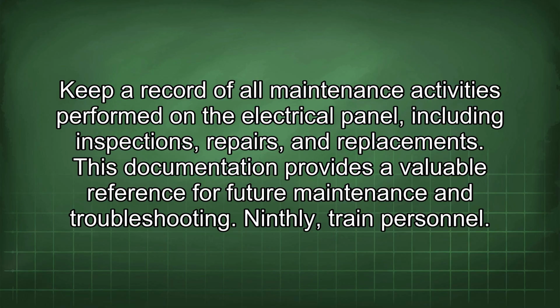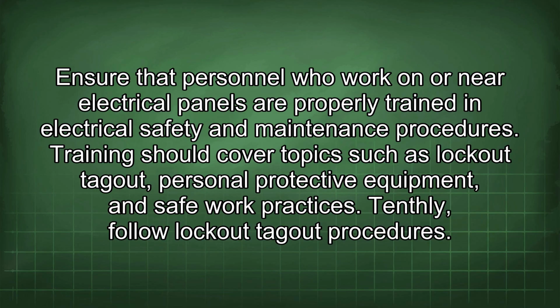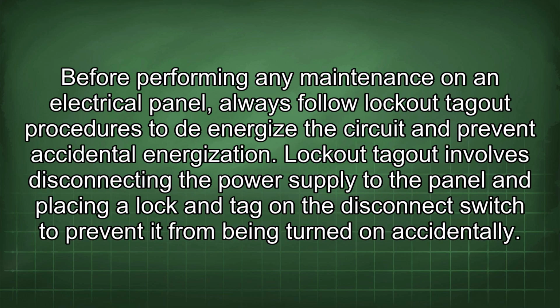Ninthly, train personnel. Ensure that personnel who work on or near electrical panels are properly trained in electrical safety and maintenance procedures. Training should cover topics such as lockout-tagout, personal protective equipment, and safe work practices. Tenthly, follow lockout-tagout procedures. Before performing any maintenance on an electrical panel, always follow lockout-tagout procedures to de-energize the circuit and prevent accidental energization. Lockout-tagout involves disconnecting the power supply to the panel and placing a lock and tag on the disconnect switch to prevent it from being turned on accidentally.